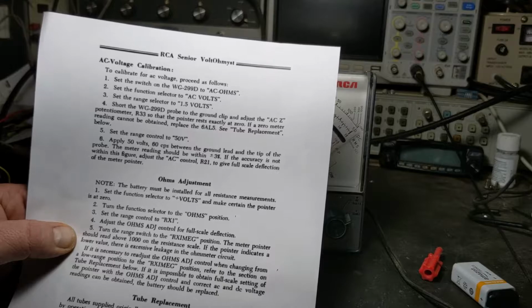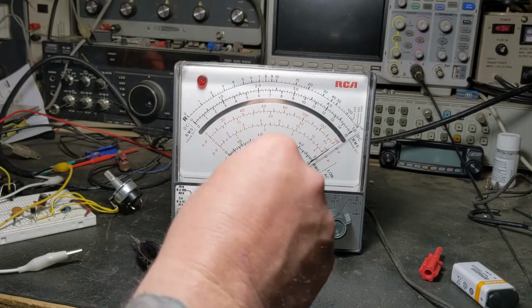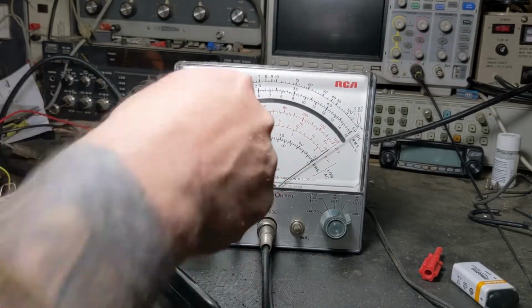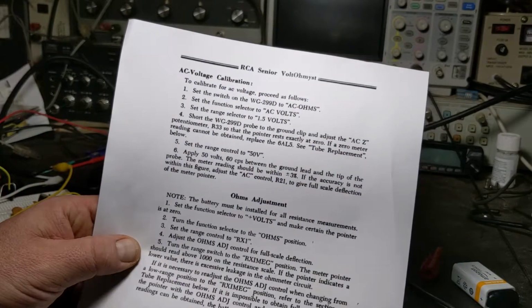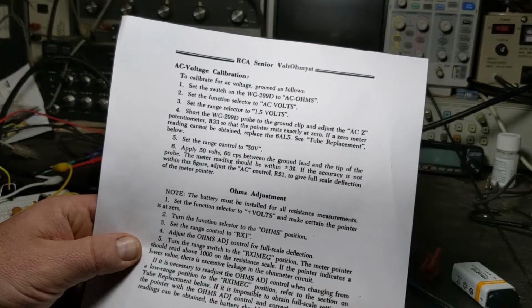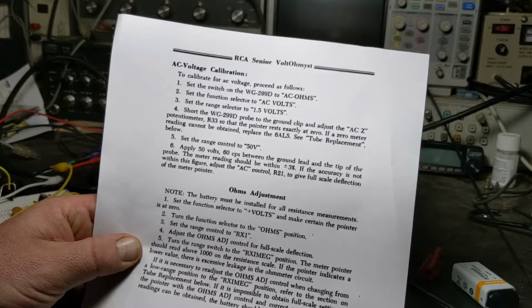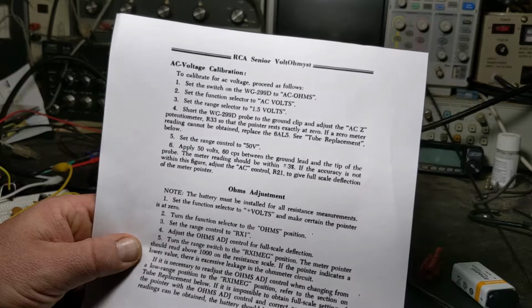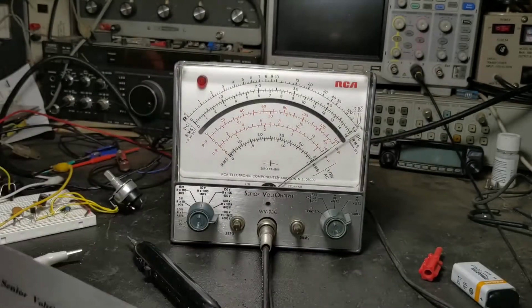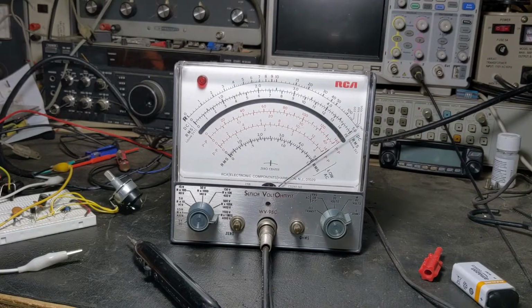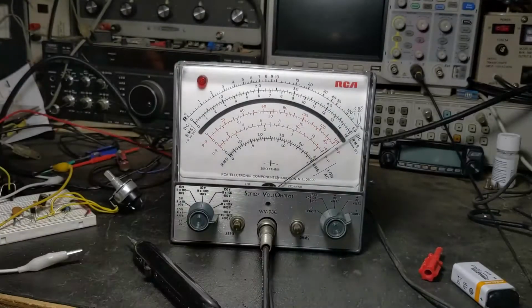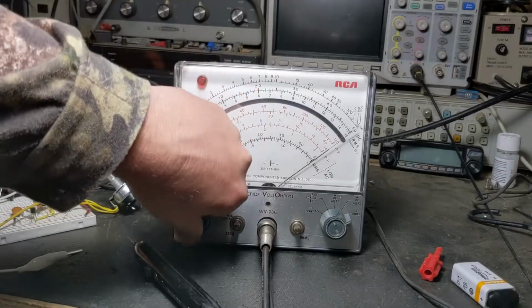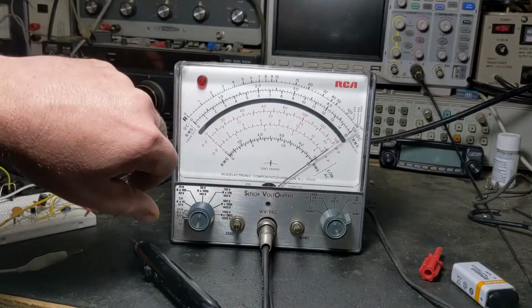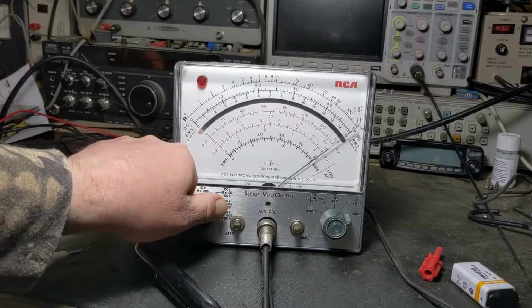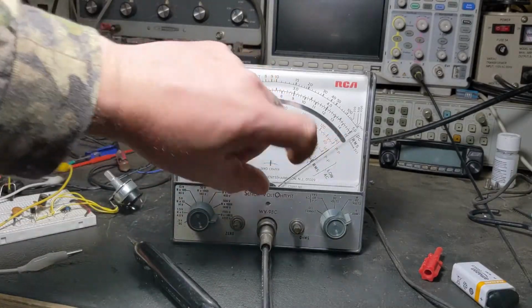And then turn range switch to R times 1 meg. Should be all the way up. The meter pointer should read above 1000 on the resistance scale. If the pointer reads a lower value, there's excessive leakage in the ohm meter circuit. And we are past 1000. It did go a little past 1000, if you notice that. We come down to times 1. Whoop, times 1 here. See, I got it on infinity. Now we move it up. See, it went up just a little bit.